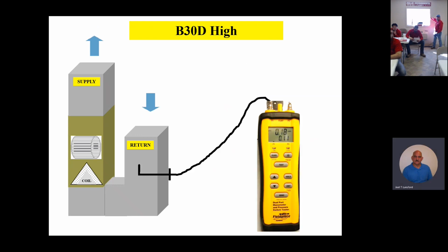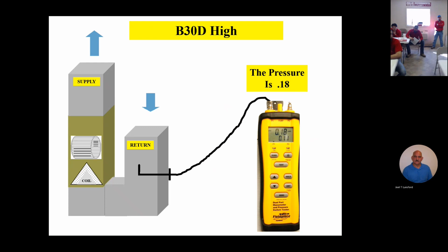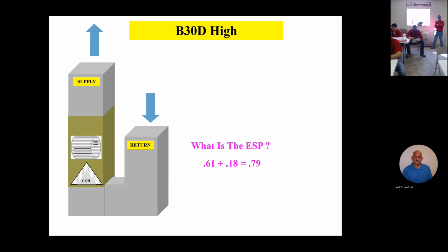So write that down, 0.61, or remember it. And our return static is 0.18, for a total of... so 0.61 plus 0.18 equals what? So there you go, 0.79. So referring to your chart, what kind of airflow are we moving on that B30D on high speed tap, at 0.79 inches of static pressure? What's the CFM?